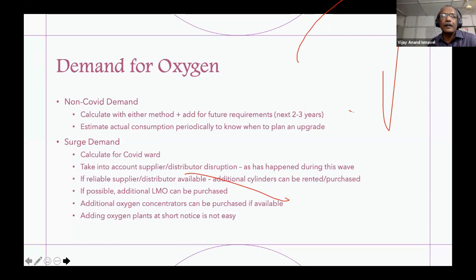For oxygen demand, you calculate the non-COVID demand the way I already mentioned. For COVID, you have to calculate surge demand because this isn't going to last the whole year, only for a particular wave. Calculate the size of the COVID ward, how many devices are connected, take into account supplier or distributor disruption, and whether liquid medical oxygen is available or not, and then decide the size. We must have redundancy, because if one source fails and another isn't available, patients will die. So ideally all four options, and depending on your situation, choose which you can add.